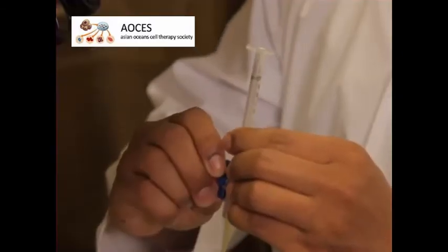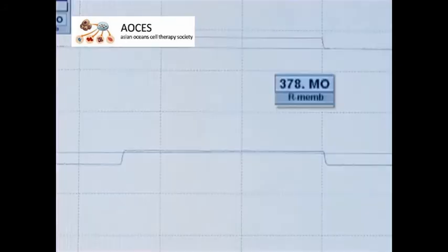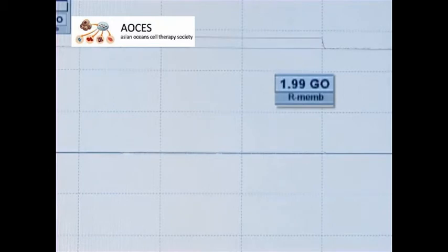To form the giga-ohm seal, gently switch from positive to negative pressure using the syringe. The formation of the seal will result in a rapid increase in resistance to greater than one giga-ohm.